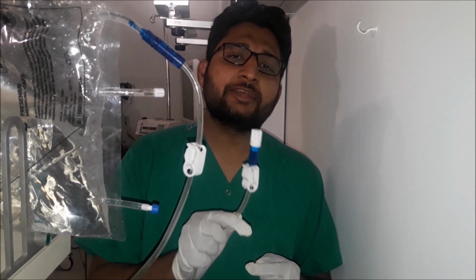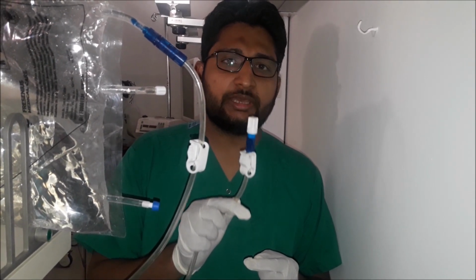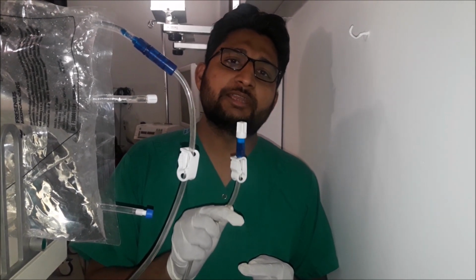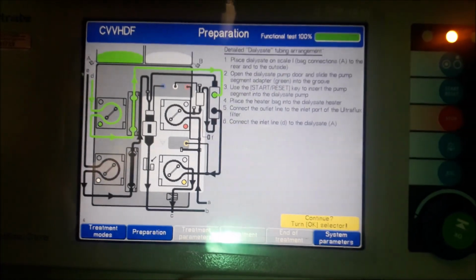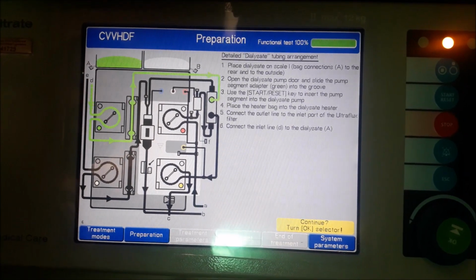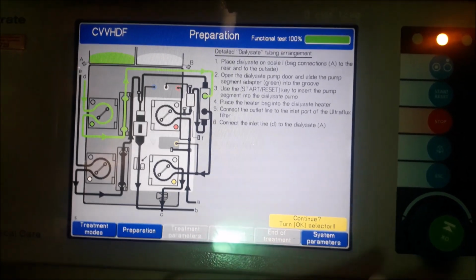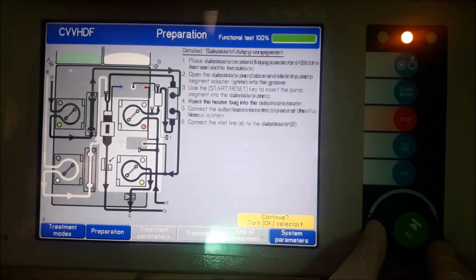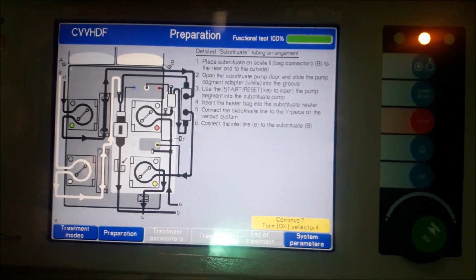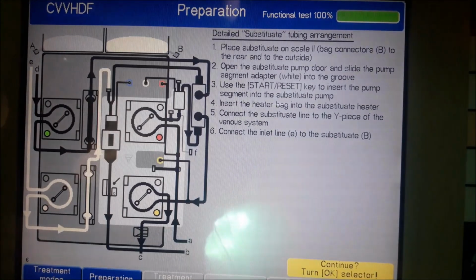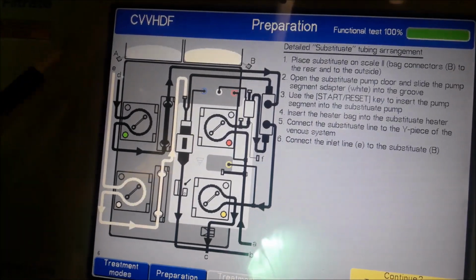We have another end of the dialysate tubing which is optional. We can use it for another bag of dialysate. All the 6 points of the dialysate tubing arrangement are completed. Now we will rotate the knob to move forward. Our next phase is substitute tubing arrangement. Let's see in the image.